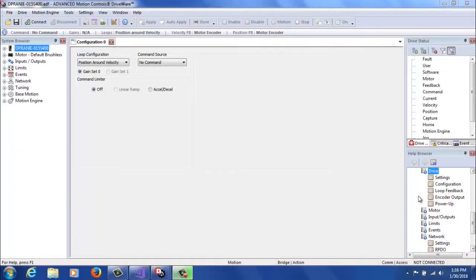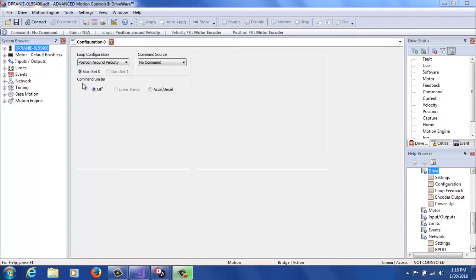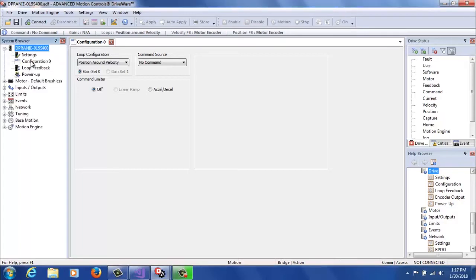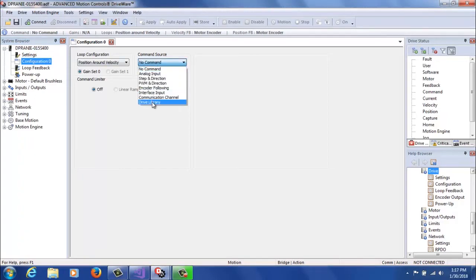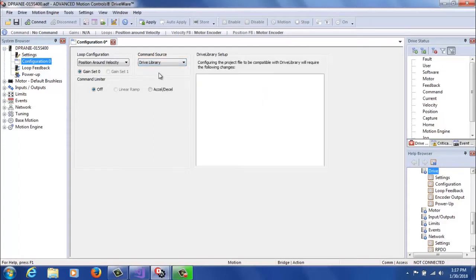Now that we've configured a project in Visual Studio, we're going to go into the system browser, and we're going to actually load up driveware, and we're going to configure a drive for drive library. We're going to start with a RS-232 drive, or one beginning in DPR or DZR, and we're going to do the only configuration you need to do for these drives, and that is go to your drive name, configuration 0, and change the command source to drive library. You'll hit apply, and if you're connected to the drive, you'll store that to the drive.